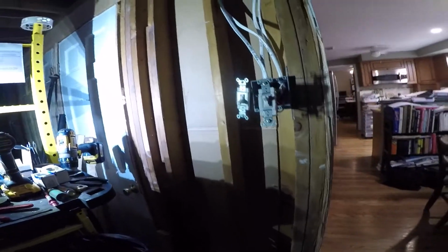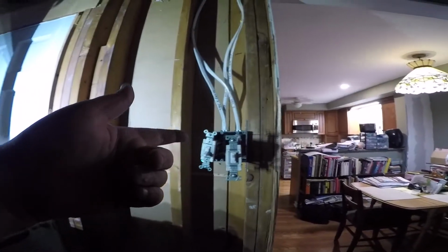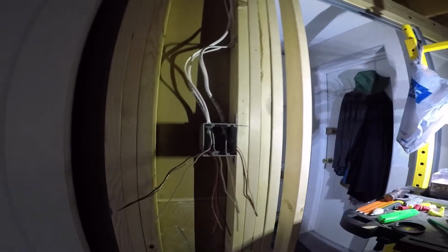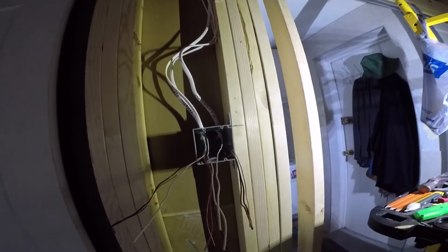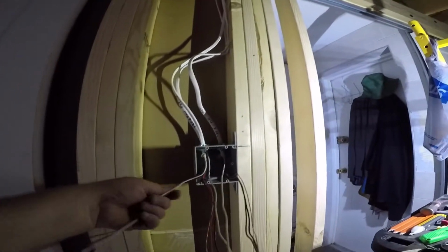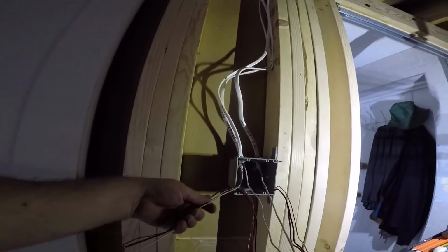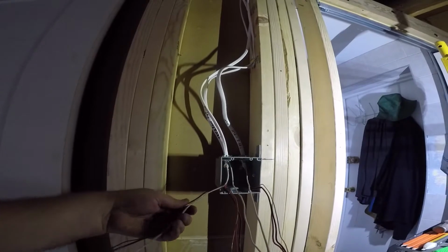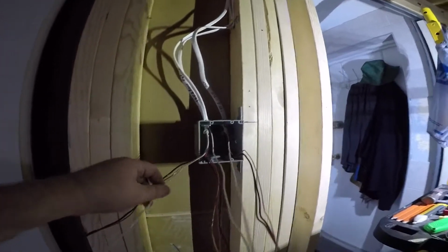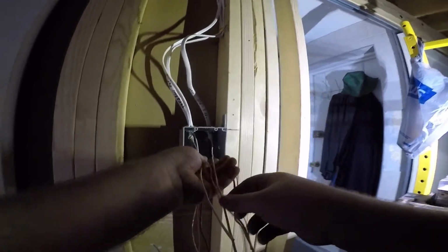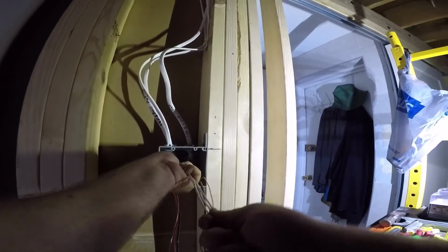Power side. We did the leg side, we did the travelers in the center. Now we got to go do the power side. Alright, so now I'm at the beginning. This is my line here. Instead of a leg going to the light, this side gets the line, gets the power. So the first thing I'm going to do is tie all the neutrals together.